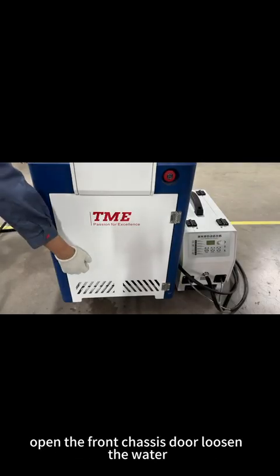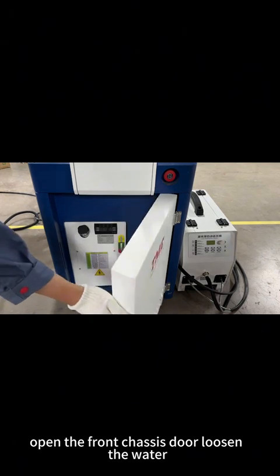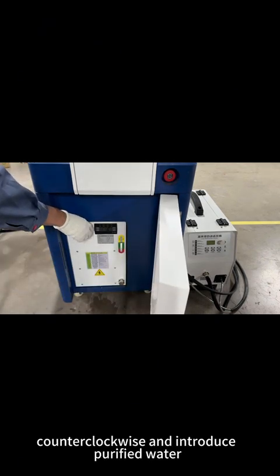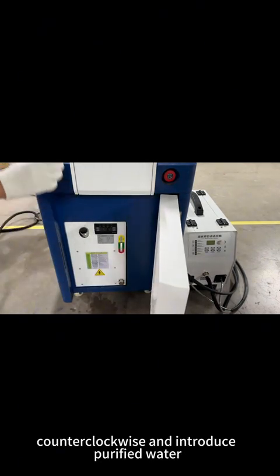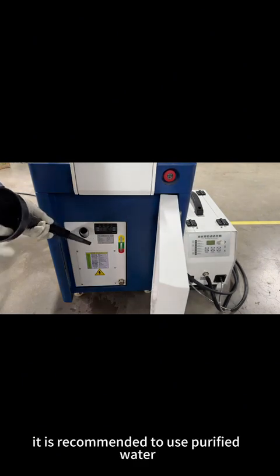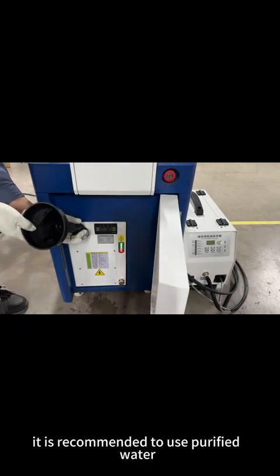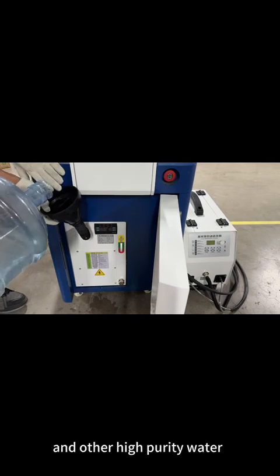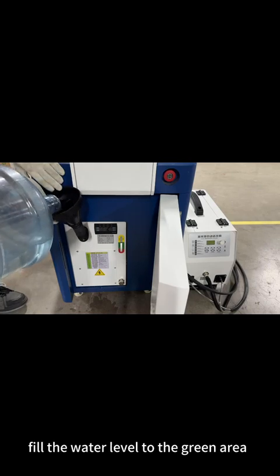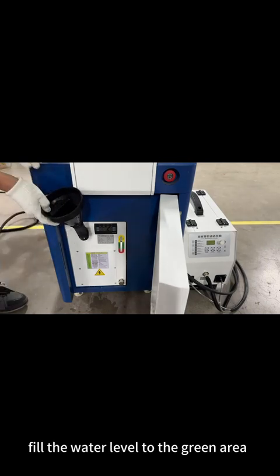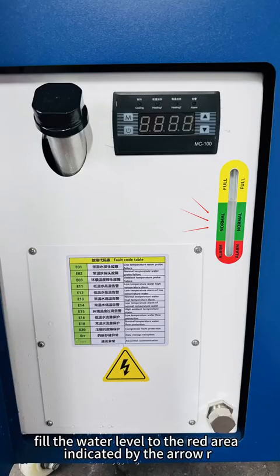Adding water to the chiller. Open the front chassis door, loosen the water inlet of the chiller counterclockwise, and introduce purified water. It is recommended to use purified water, deionized water, and other high-purity water. Fill the water level to the green area. Fill the water level to the red area indicated by the arrow.